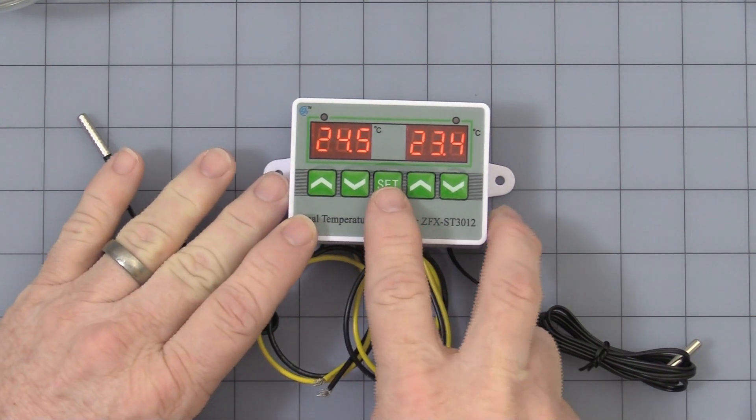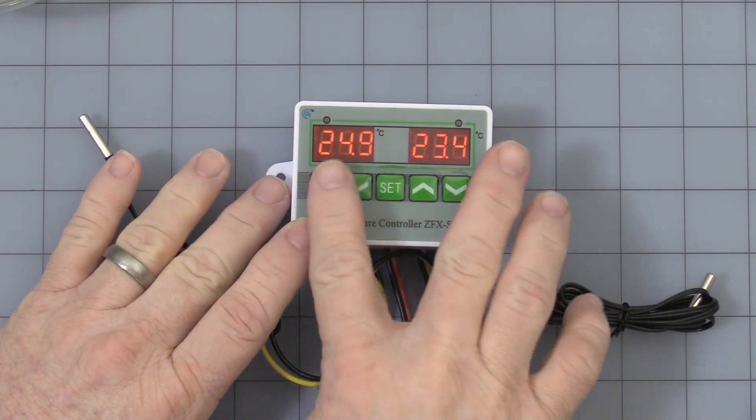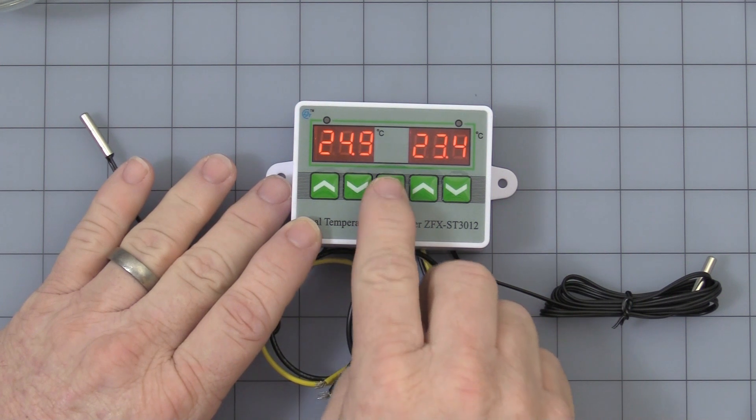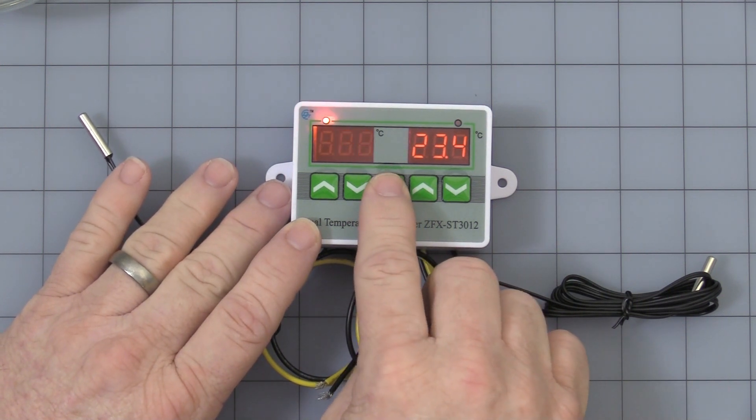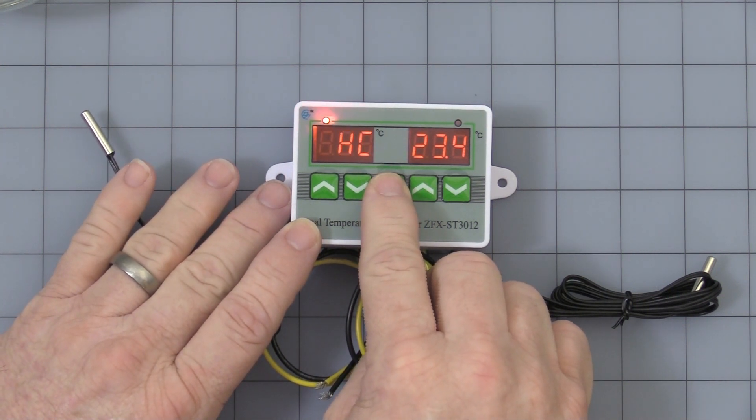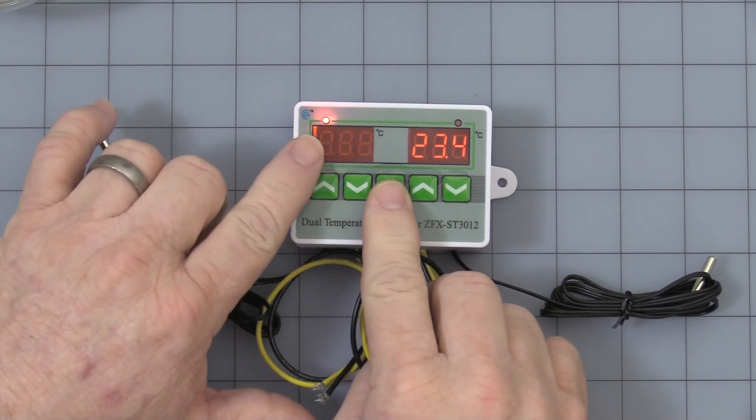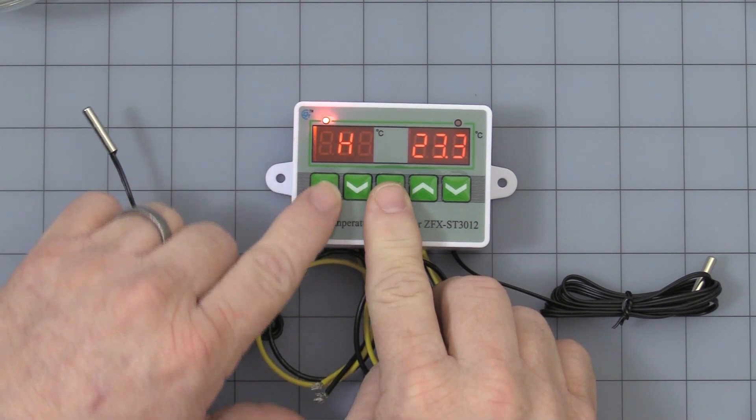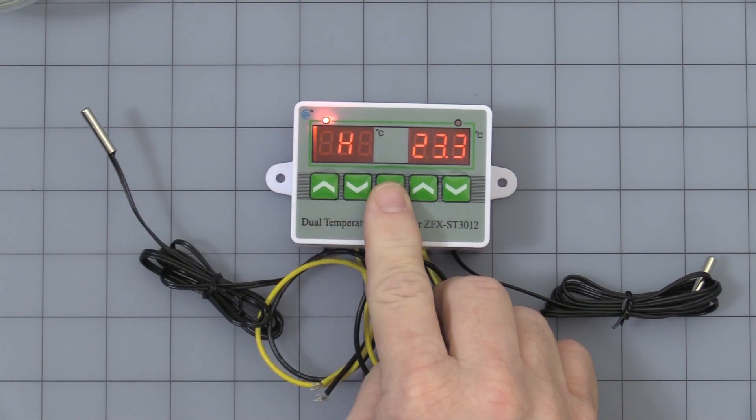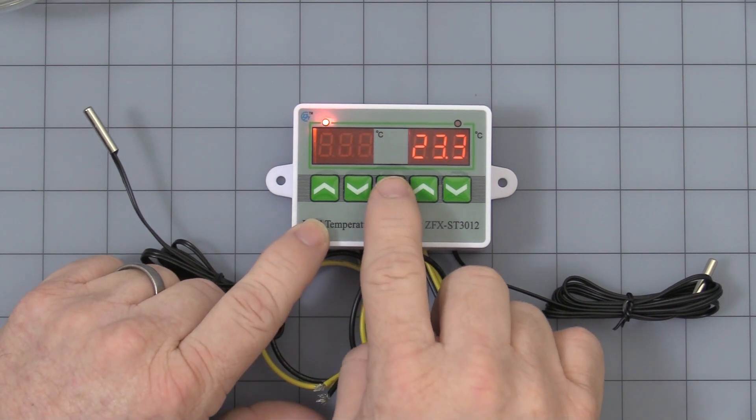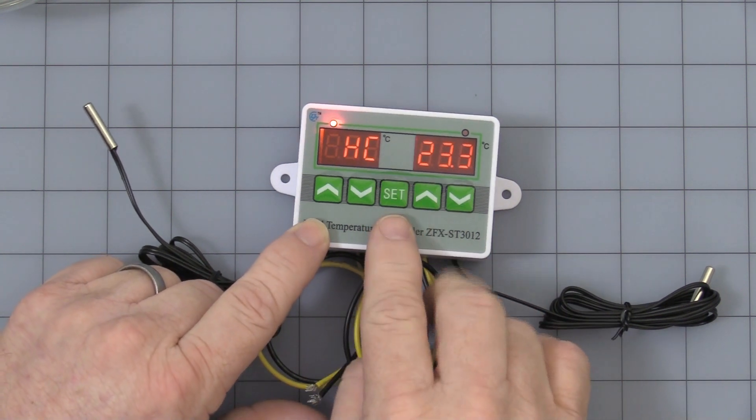Now to get into programming, programming is the same for both sides. It depends on what side is flashing is which side you're going to program. So let's start with press the set, then press and hold set again. Now you get an HC. Press the set again. This is factory set at C for cooling mode or heating mode. Let's stay in the cooling mode. I think that's what most people will use.